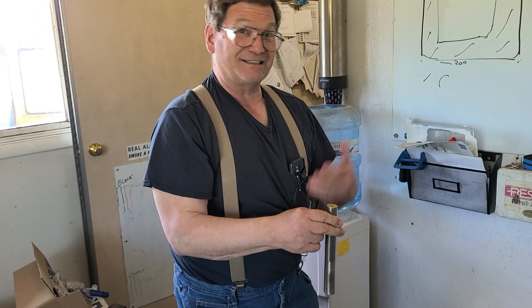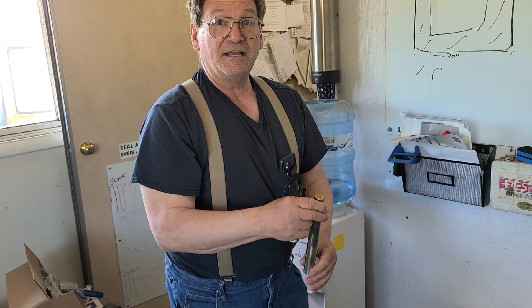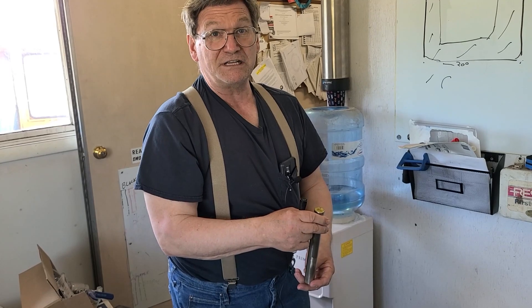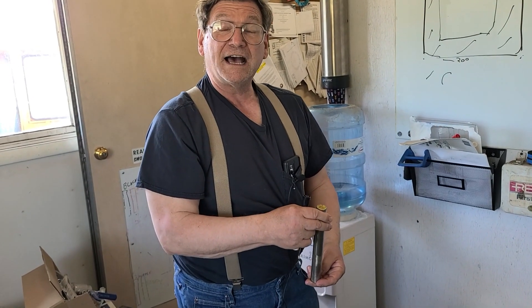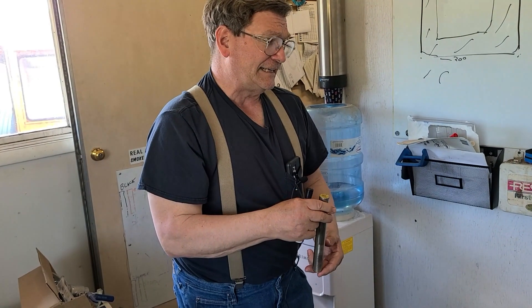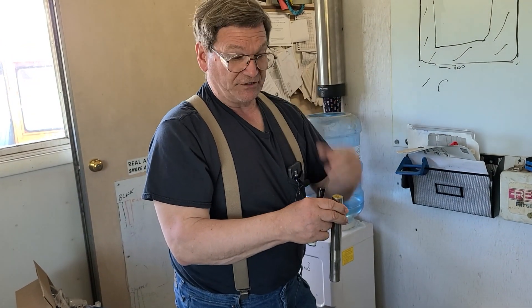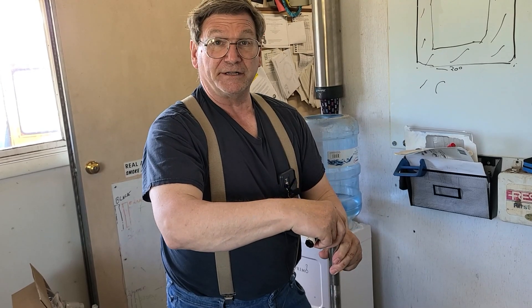Sometimes they'll use plastic, some have rubber, but they stabilize all these pieces of shaft. They'll be anywhere from 20 feet deep — I don't know what the total depth was on this one, I had to make the top shaft three and a half inches longer. I've worked on ones that were a couple hundred feet deep. Each section of shaft has a left-hand thread on it.